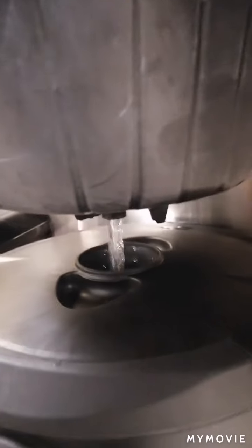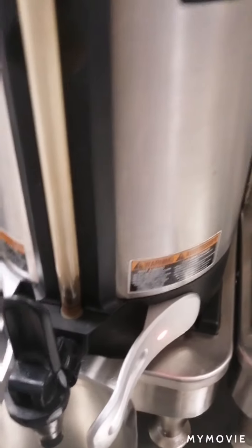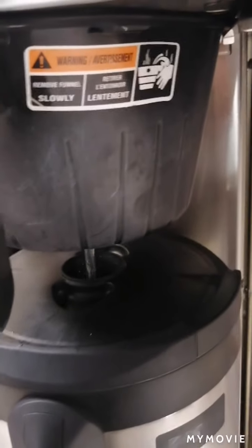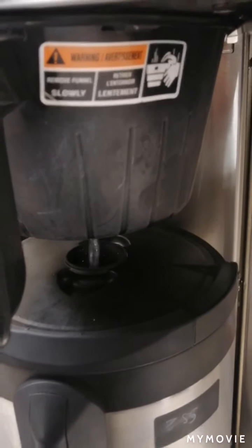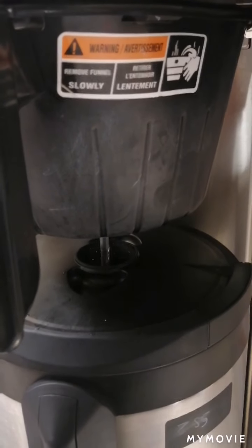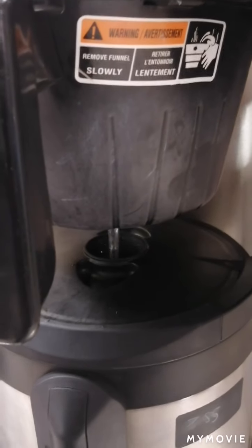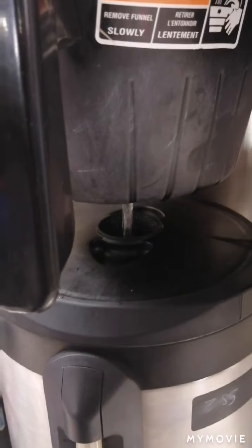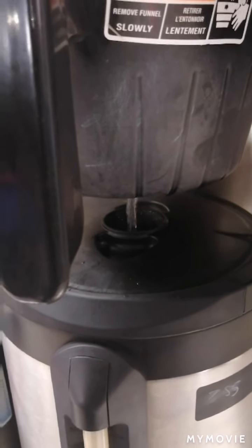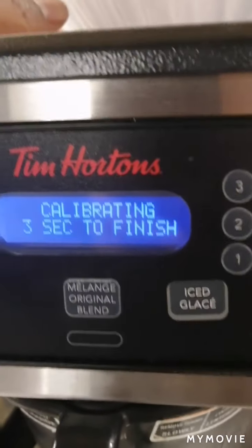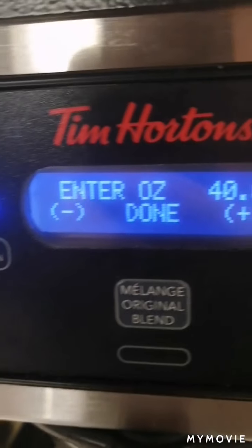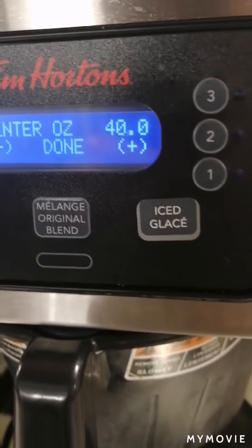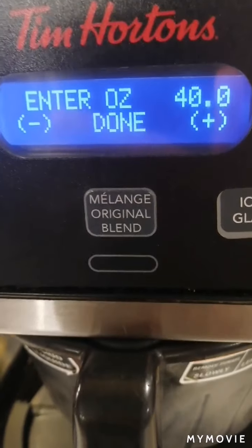When the machine finishes counting down, it will stop, and once it stops, you will dispense the water that comes out of the machine into your 64 ounce graduating cylinder. See, I have it there underneath the craft. Then you will put it on the scale and weigh it. The machine will give you the amount that it thinks it dispenses, but you will weigh the amount that it actually dispenses, and then you will put that amount in the machine.